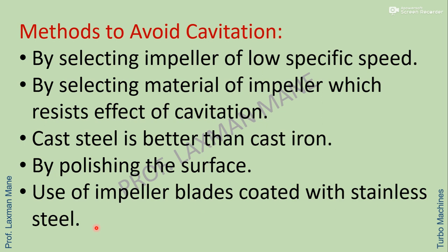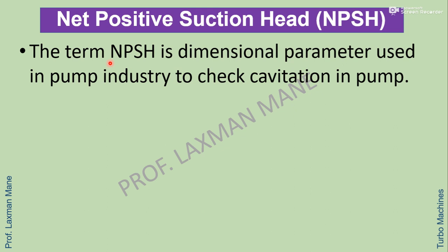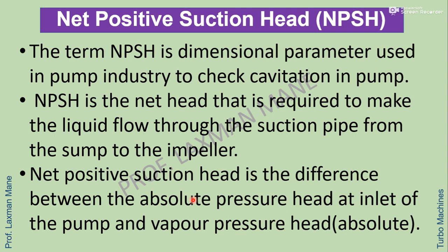Now we will discuss about net positive suction head, meaning NPSH. The term NPSH is a dimensional parameter used in the pump industry to check cavitation in a pump. NPSH is the net head required to make the liquid flow through the suction pipe from the sump to the impeller. Net positive suction head is the difference between the absolute pressure head at the inlet of the pump and the vapor pressure head.